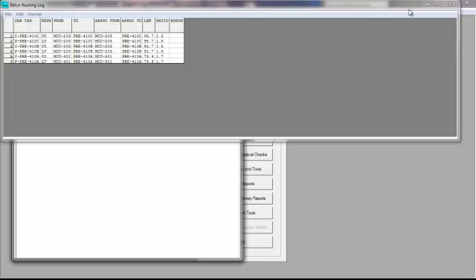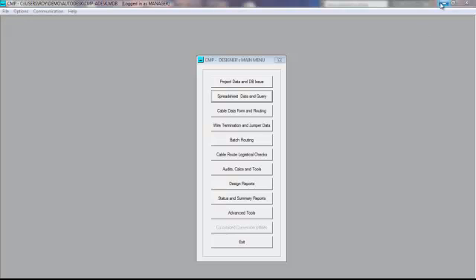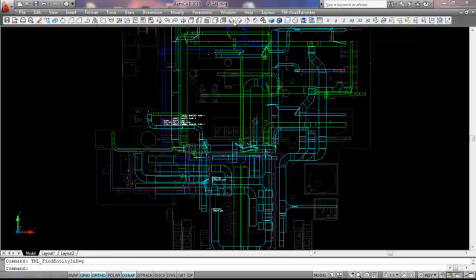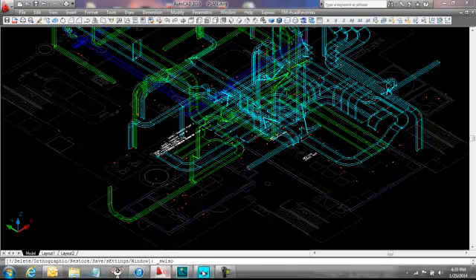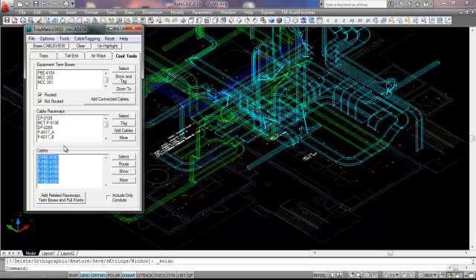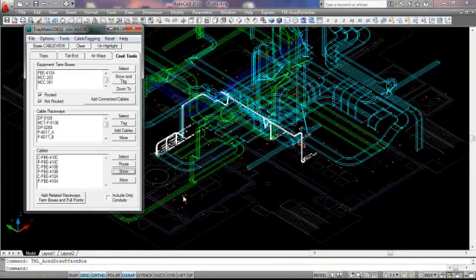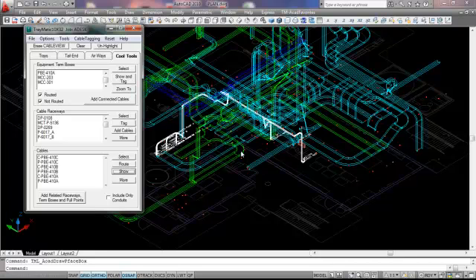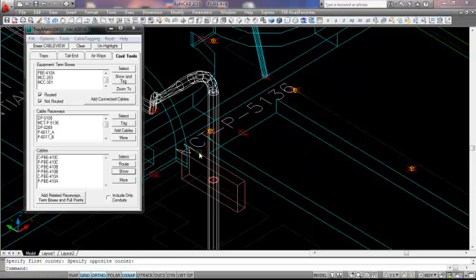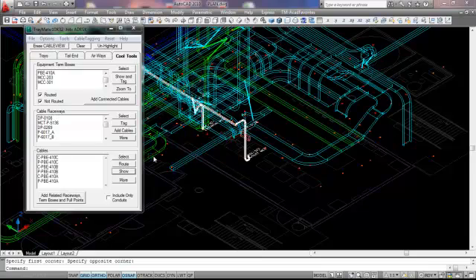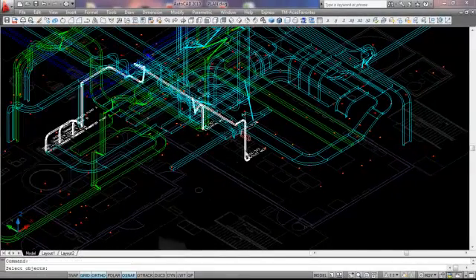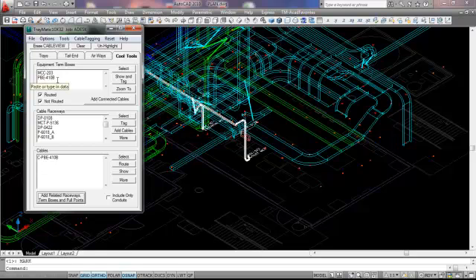So now that we've routed those cables, let's see what they look like. I'm going to show those cable routes and the raceways. You can see them in the raceways coming from the motor control center. It will identify the MCC. It's going through MCTP 5136, so it's also showing that. Let's take a look at one cable. If I clear my list here and select a particular cable, I can hit this button again and that's going to tell me it's going from MCC 203 to PBE-410B and this is the list of raceways that it's actually following.